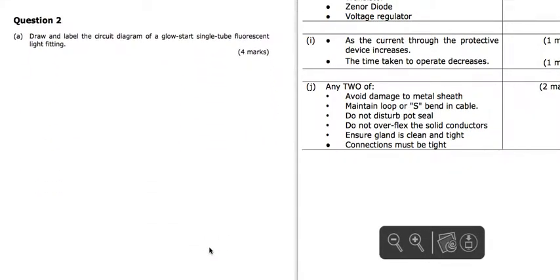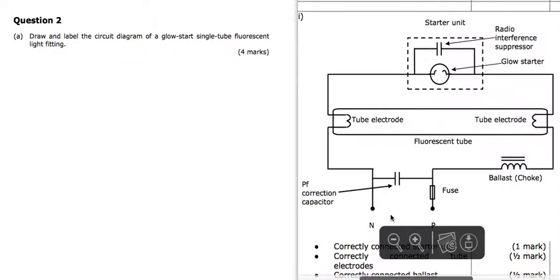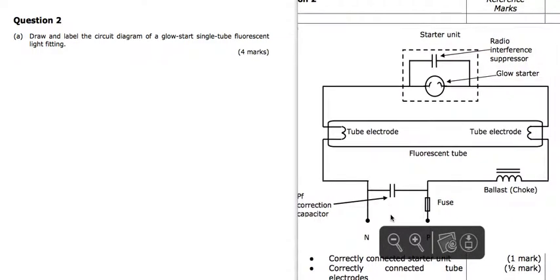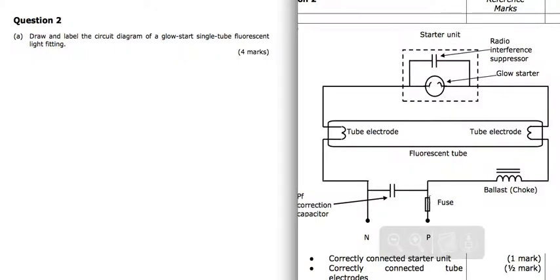Draw and label the circuit diagram of a glow start single tube fluorescent light fitting. So here's our diagram there. We've got our phase and fuse feeding the ballast or the choke. It feeds one end of the tube through the starter, through the other end of the tube, back to the neutral. And we've got a power factor correction capacitor there and a radio interference suppressor capacitor there.